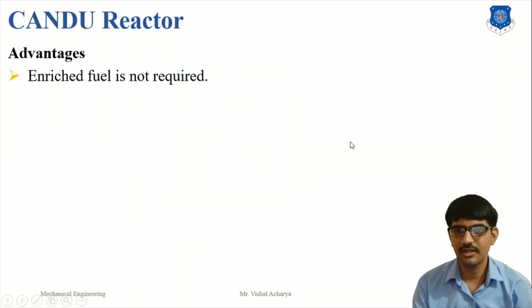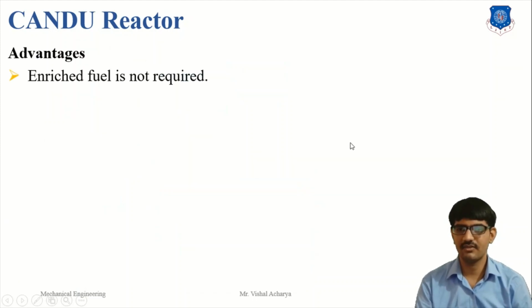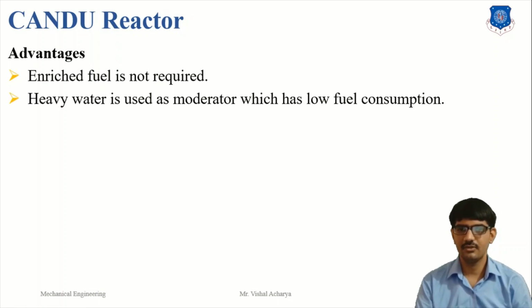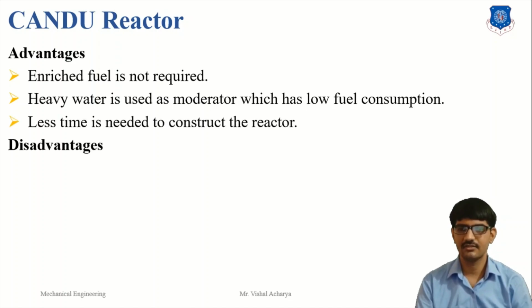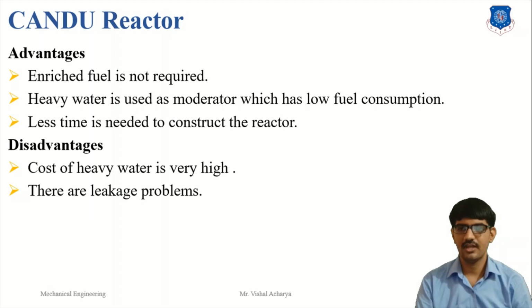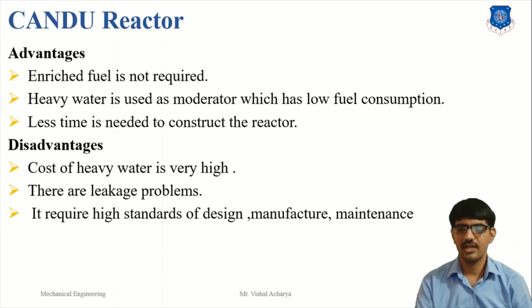The advantage of the Candu reactor is that enriched fuel is not required, so the fuel cost is very low. Heavy water is used as a moderator, which gives low fuel consumption. Less time is needed to construct the reactor. Here are some disadvantages also. First, the cost of the heavy water is very high. There is a leakage problem also, and it requires high standards of design, manufacture and maintenance.